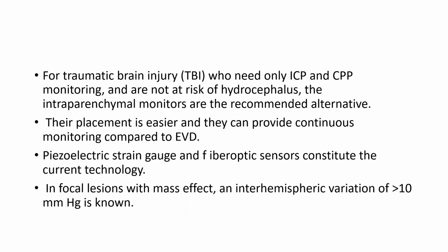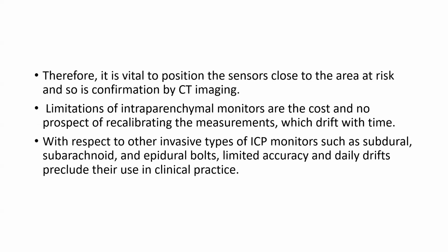hydrocephalus. The intraparenchymal monitors are the recommended alternative. This placement is easier and they can provide continuous monitoring compared to EVD. Piezoelectric strain gauge and fiber optic sensor constitute the current technology. In focal lesion with mass effect, an interhemispheric variation of more than 10 mmHg is known. Therefore, it is vital to position the sensor close to the area at risk, and so is confirmation by CT imaging. Limitations of intraparenchymal monitors are the cost and no prospect of recalibration, as the measurement drifts with time.